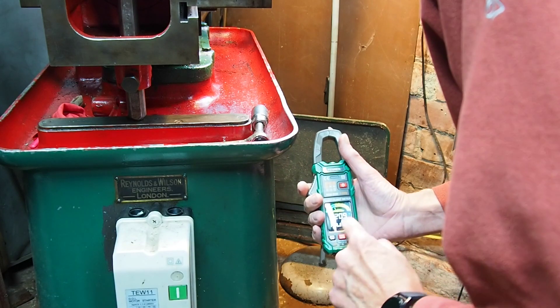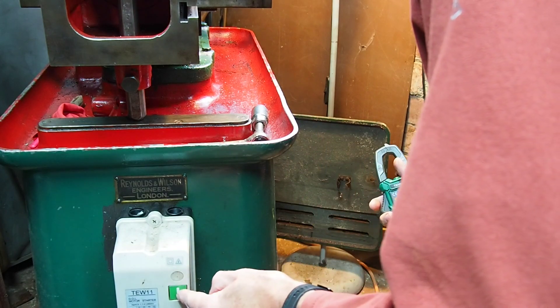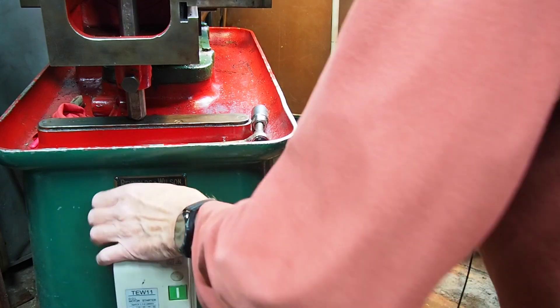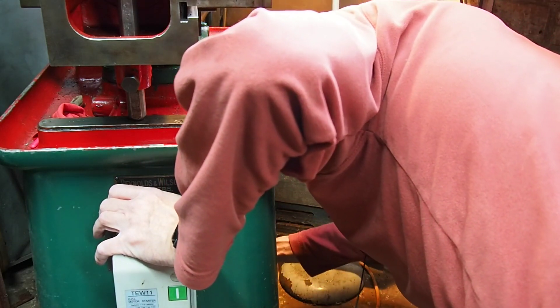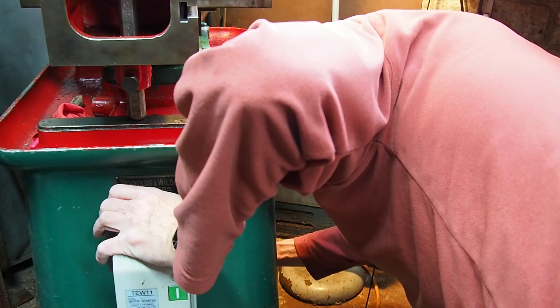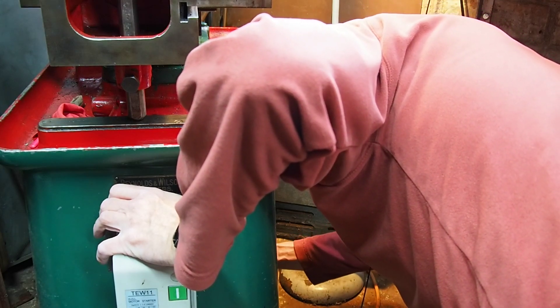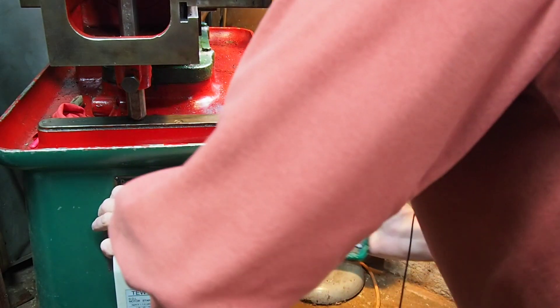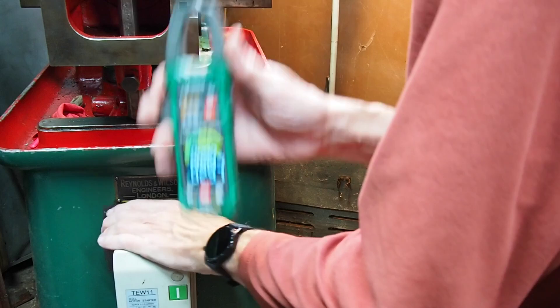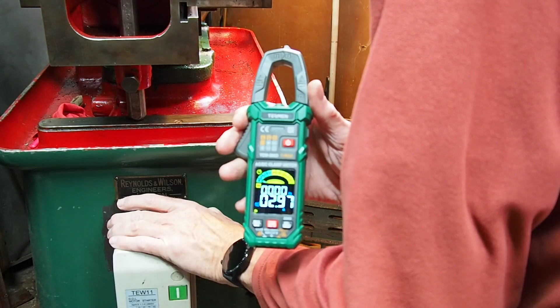The meter's on auto. I'm going to start the motor like so and grab the middle conductor there. Hopefully I'm going to get a reading. Yeah we've got a reading, so I'm going to press hold. There we are, 2.97 amps. Hopefully you can see that there.